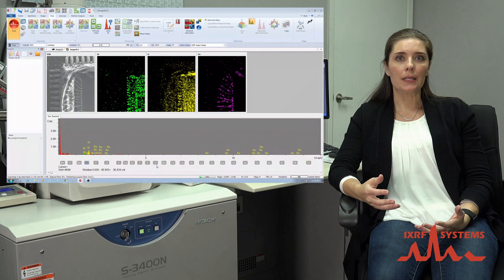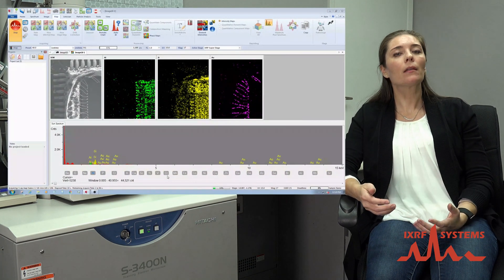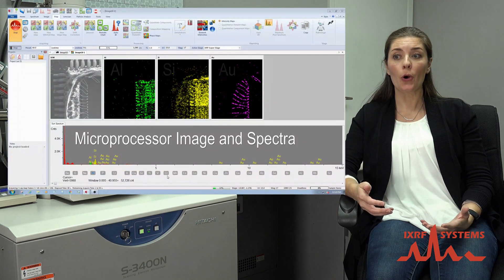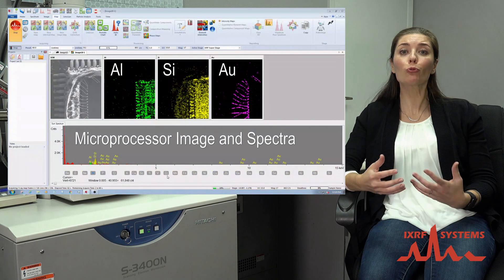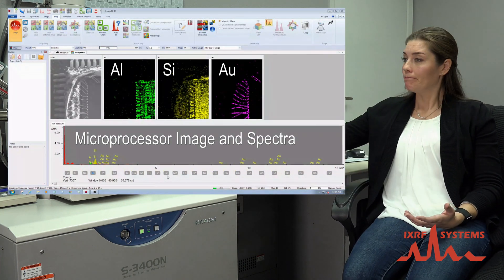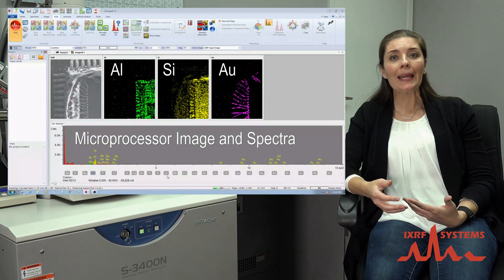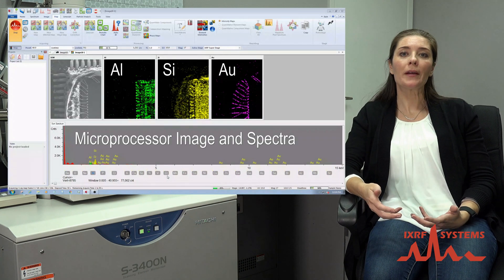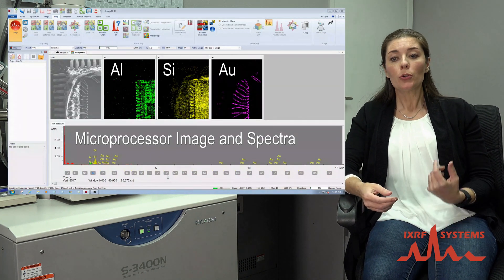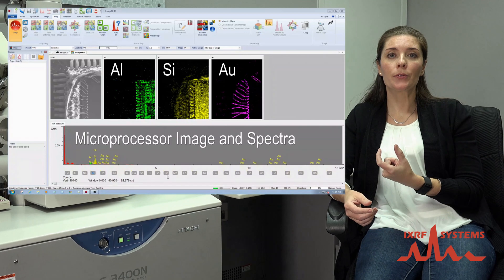What the heck is EDS? Energy Dispersive Spectroscopy. So really what that means is it allows us to get elemental information from our samples. Having an electron microscope, we get these great images but they're just images. By adding EDS, we can actually get elemental information — not only what's in our samples but where it is located. Spatial variation within the material can be collected through what we call mapping.